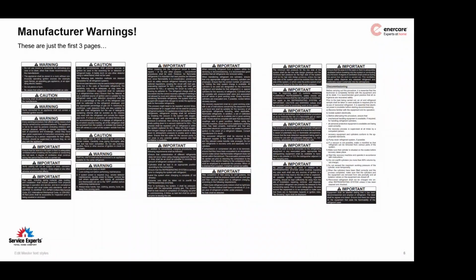There is some really good reading in these manuals. Specifically, the Lennox seem to be a little more well-rounded, a little more comprehensive. So if you're going to get online and start reading some manuals, these are definitely good ones. The Carrier manuals and the Goodman, Amana, Daikin manuals were reasonable, but they just didn't seem to be quite as comprehensive as the Lennox stuff. So I would strongly encourage you to take a minute and go through these warnings and cautions and better understand what the manufacturer is trying to spell out, so that you know you're working safely before you jump into any A2L based installation.